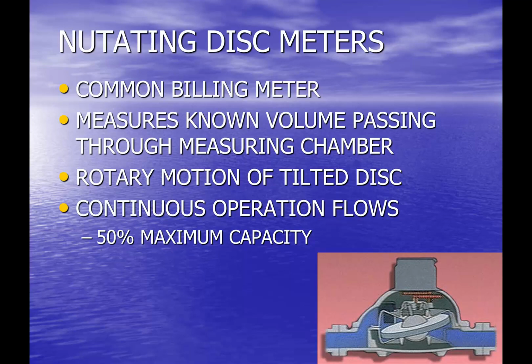So you're going to range in that 5/8 inch to 2 inch size from about 20 gallons per minute to 160 gallons per minute as far as its maximum capacity. And then keep in mind that typically we want to operate these meters at somewhere around half of their maximum capacity in order to not overly stress or wear the meter. So when operated properly, these meters are very accurate at flow rates as you go up to the 2-inch meter size.